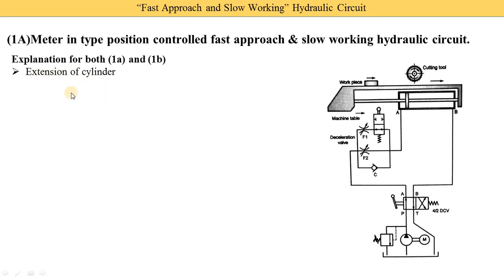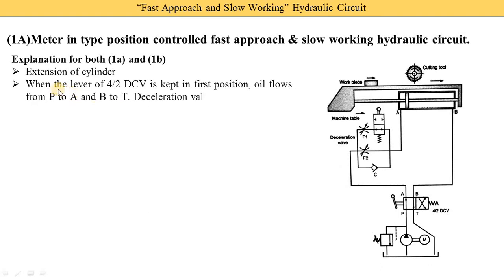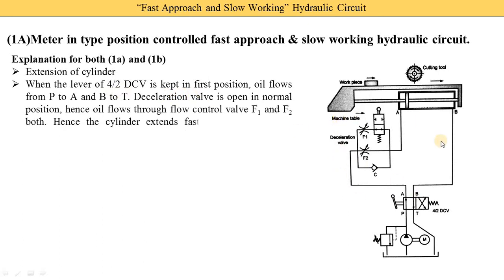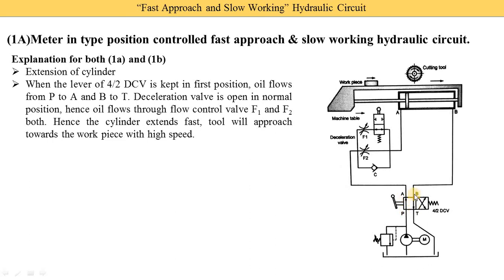Fast approach and slow working is generally for the extension of the cylinder. When the lever of the 4/2 DCV is kept in the first position, oil flows from P to A and B to T. The P-port is connected with the A-port with the arrow in the upward direction, and the B-port is connected with the T-port with the arrow in the downward direction. The deceleration valve is open in the normal position, so oil flows through flow control valves F1 and F2 both.